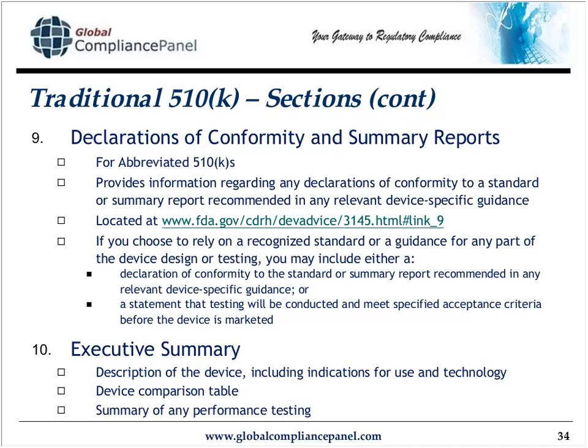the statement. Section 10 is the executive summary. It's a description of the device, indications for use, a couple of words on the technological aspects of it, a device comparison table between your device and the predicate device. We've already gone over previously the ways to identify substantial equivalence and a summary of the performance testing that was done.